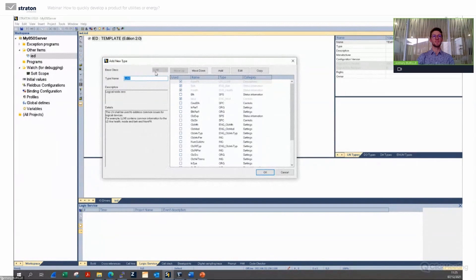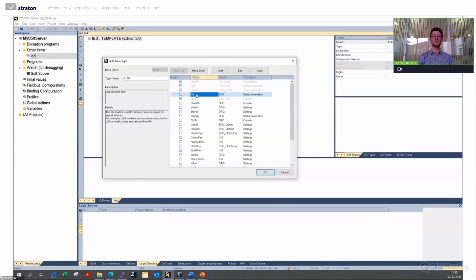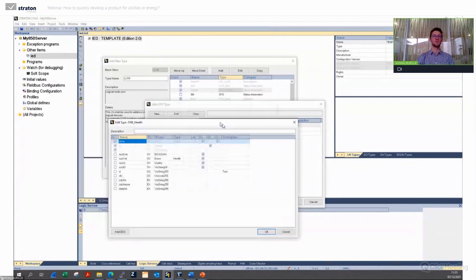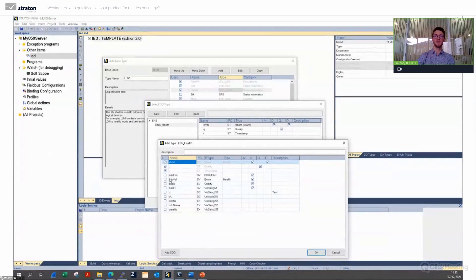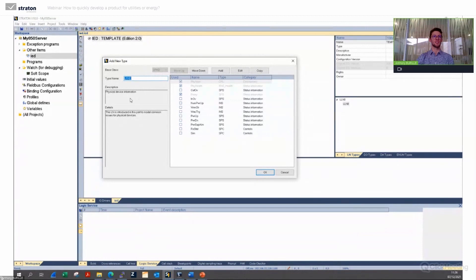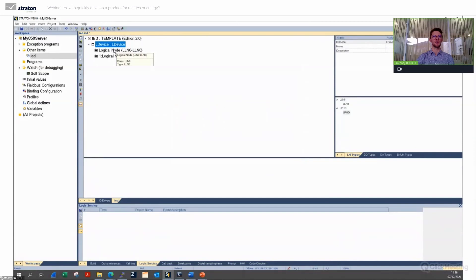I choose the name and open it — I can see a simple graphical editor. At first we insert a new logical device describing our substation capabilities. We can choose between Edition 1 or Edition 2 — depending on what you choose you will have more or less logical nodes, logical devices, and data objects, which is strongly linked to the standard. By default it proposes declaring Logical Node Zero, with a description and every mandatory data objects shown in gray, plus optional ones.